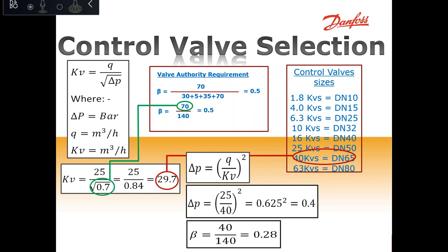So if we take any two-way valve selection, the authority of the valve, which most of the specifications will call for 0.5, is actually never 0.5 except in the index unit. The last unit, available system pressure is less, then the authority of the valve is better. That's why you can find that air handling units, etc. are having a good control ability versus the FCUs, etc. But using a DPCV, you will equalize the available system pressure everywhere in your network.